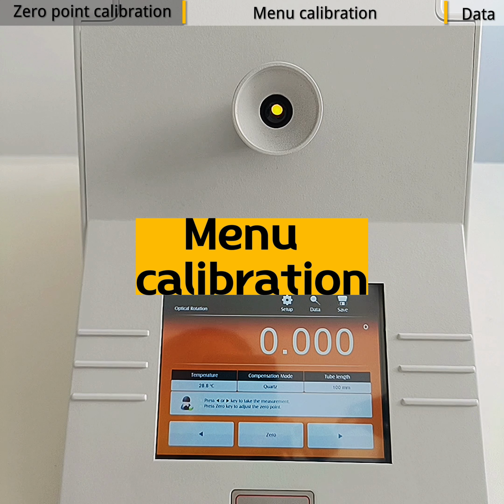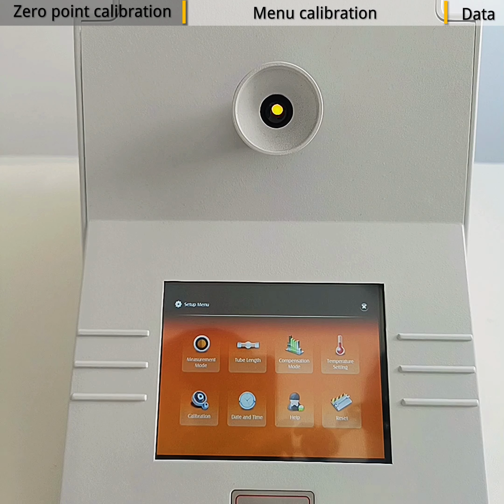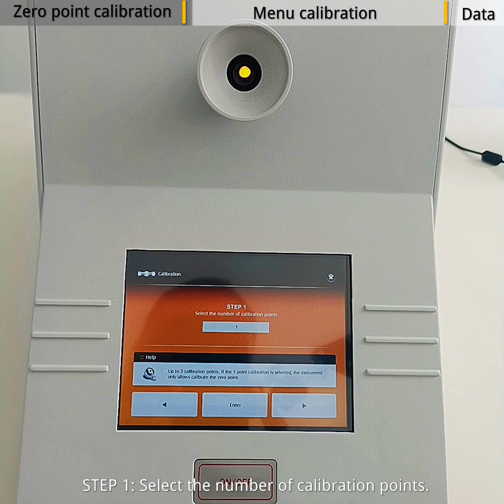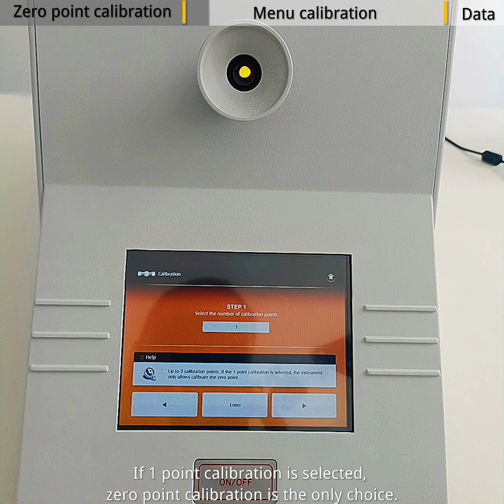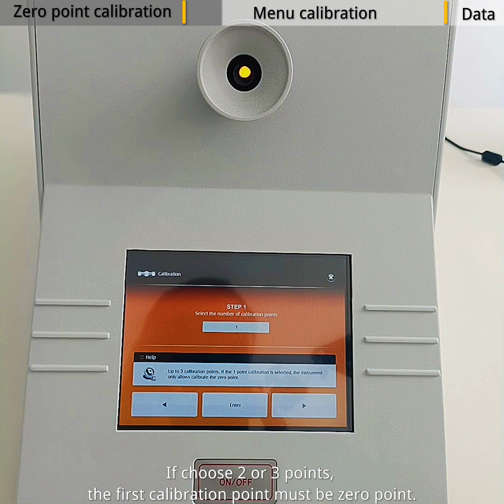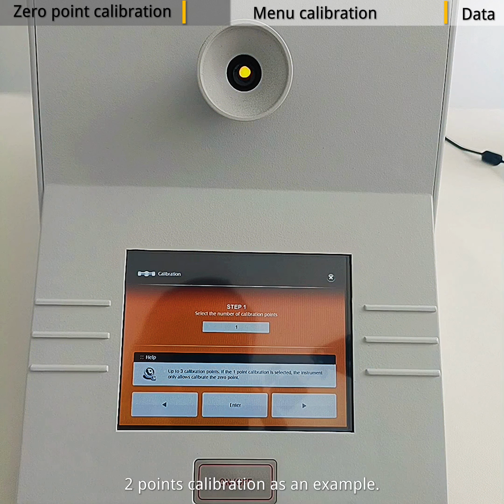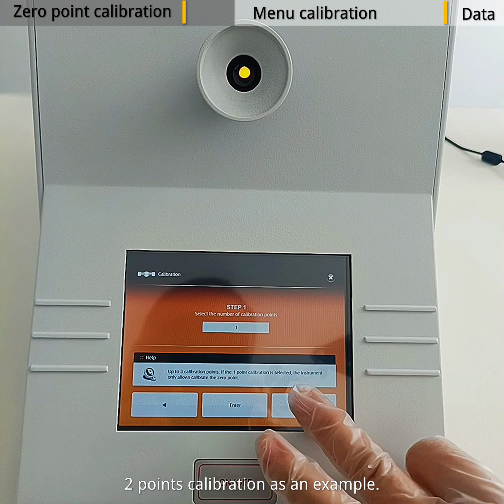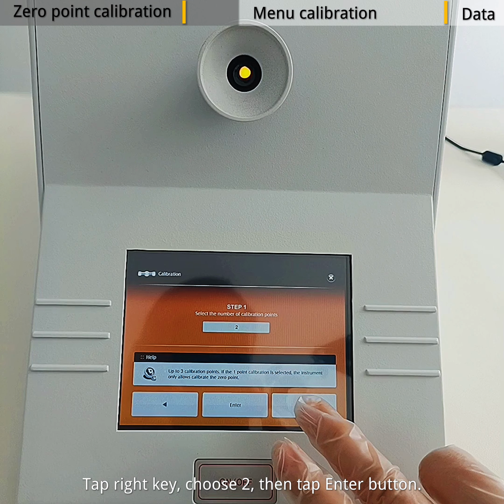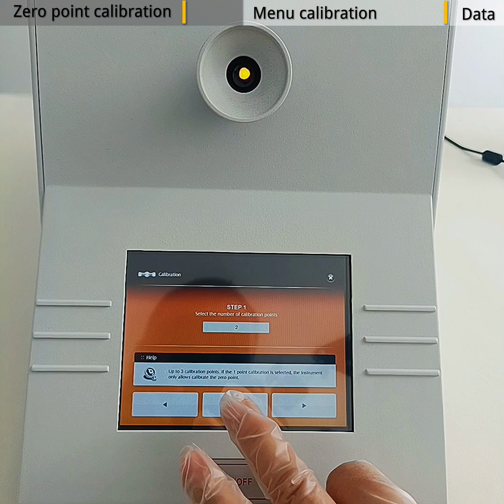Then Demo menu calibration, tap Setup. Tap Calibration. Screen shows Step 1, select the number of calibration points. 1 to 3 points calibration are optional. If 1-point calibration is selected, 0-point calibration is the only choice. If choose 2 or 3 points, the first calibration point must be 0 point. 2 points calibration as an example. Tap right key, choose 2, then tap Enter button.